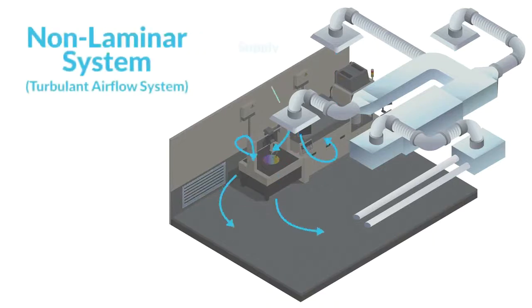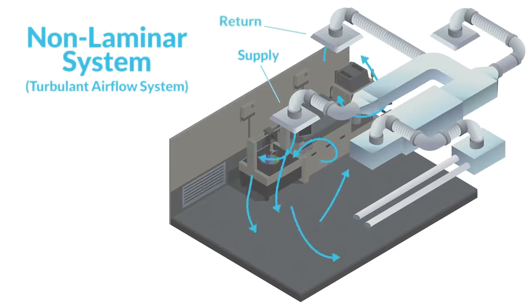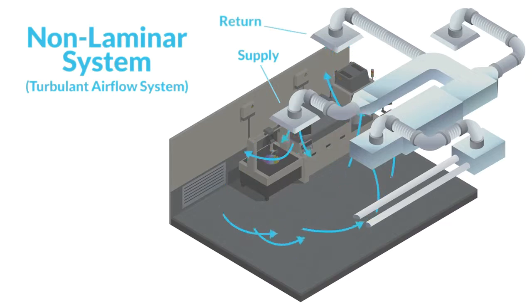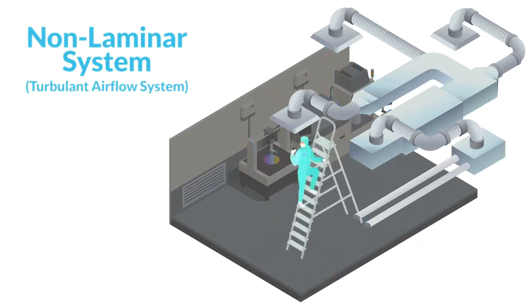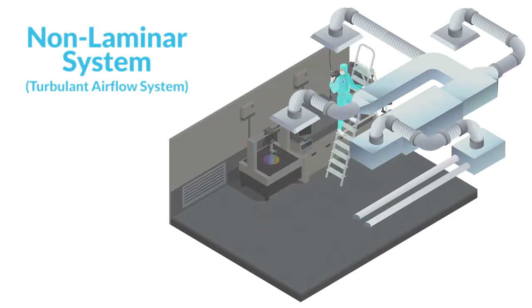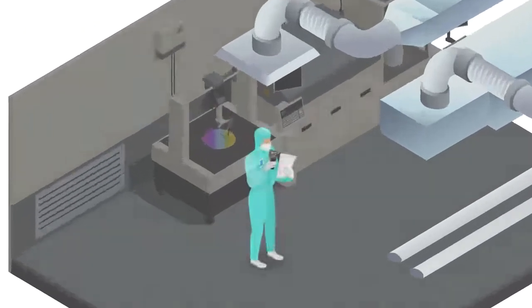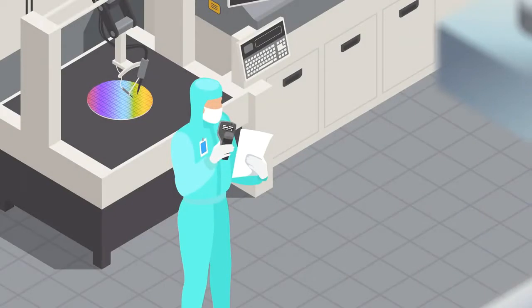In this case, the room is designed to dilute and remove contaminants based on a certain number of air exchange rates per hour. To check this type of system, you would measure the airflow at both the supply and the returns, and then calculate the number of air exchanges that occur per hour. After you've collected your data, it's time to compare your results with the design specifications for the room.